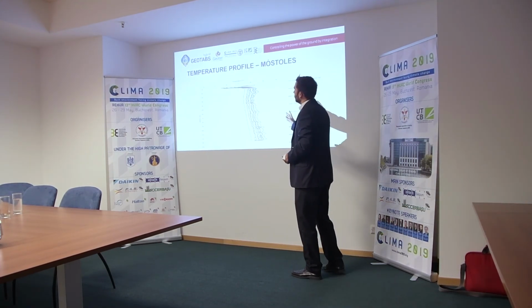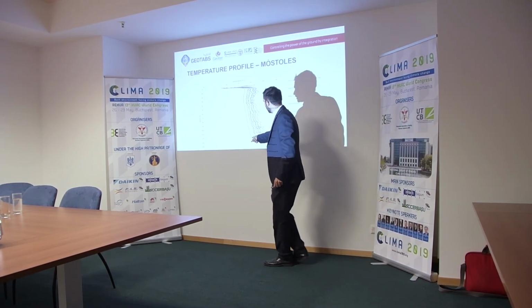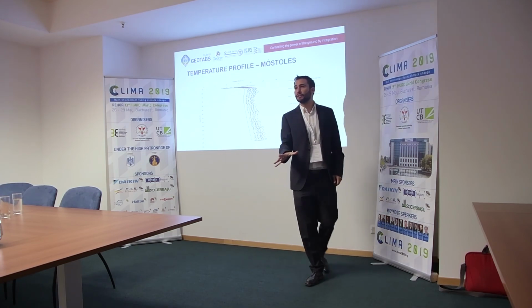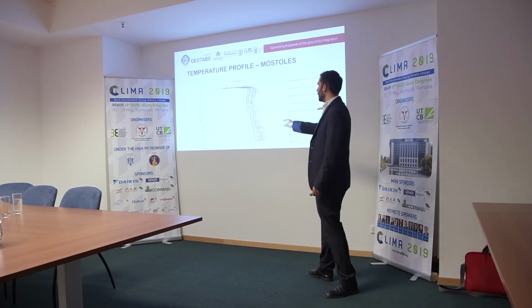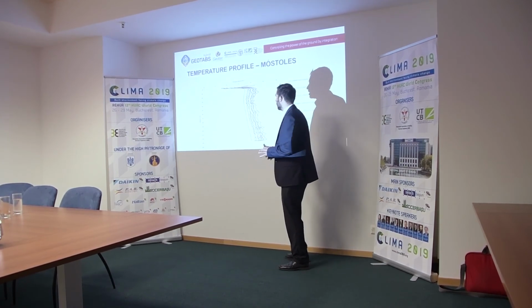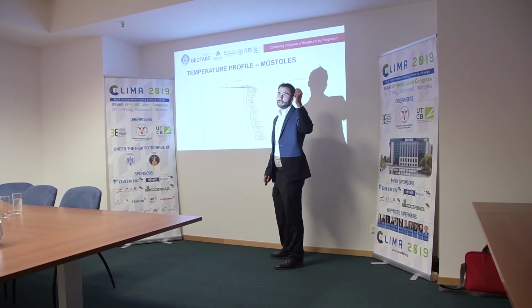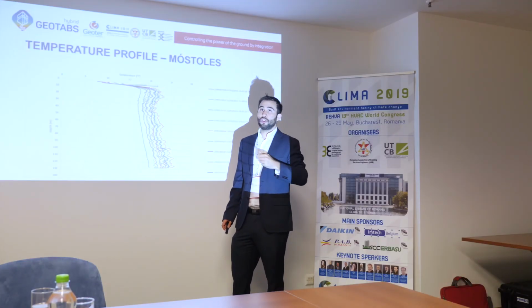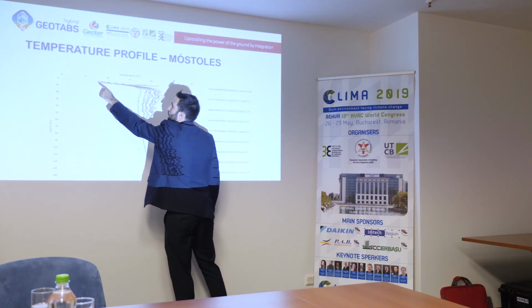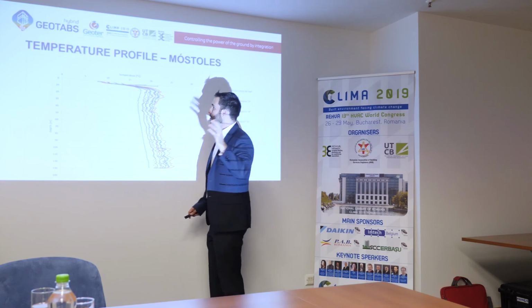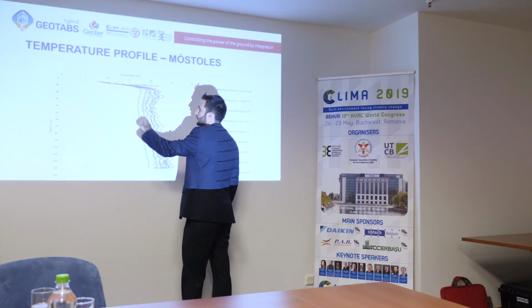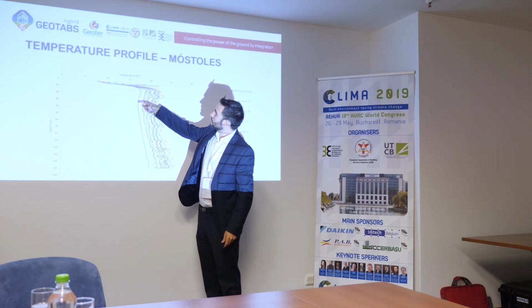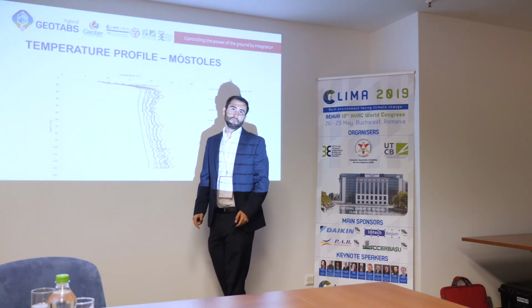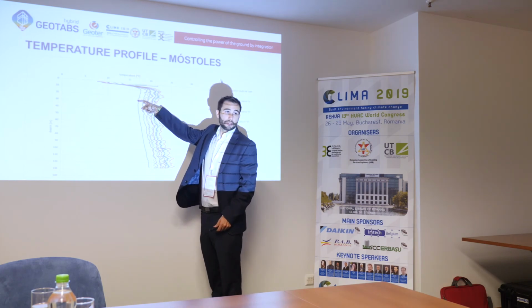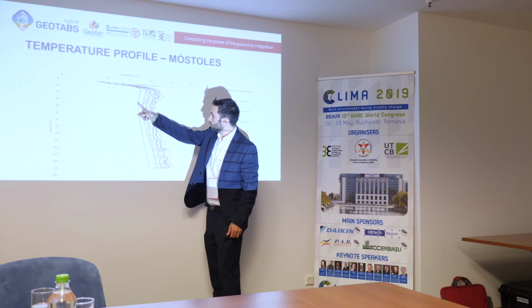Here you can see the result. This is the temperature profile. The first curve here in blue color is the unaltered temperature of the borehole. This is without introducing heat into the ground. If you remember the diagram of the geothermal I showed you before, here at the surface we have around 7 degrees, but as we go deeper and deeper, we can see the stabilization of the temperature more or less at 25 meters depth, when we have around 17.5 degrees. And at this moment, we can see the gradient, 3 degrees per 100 meters.